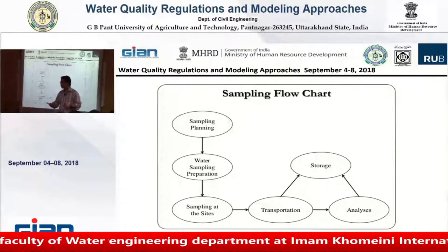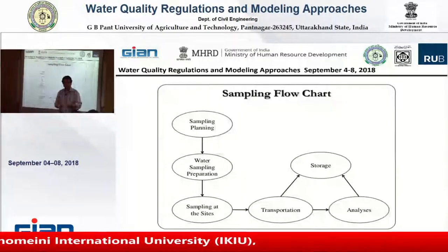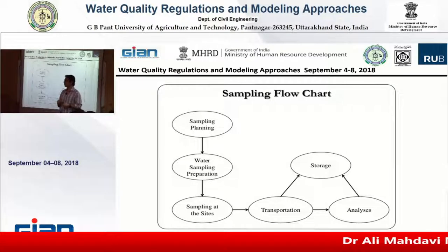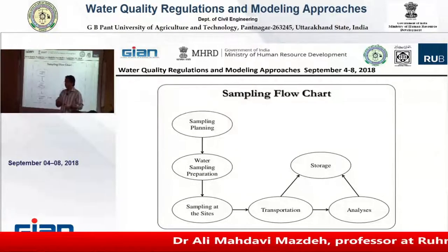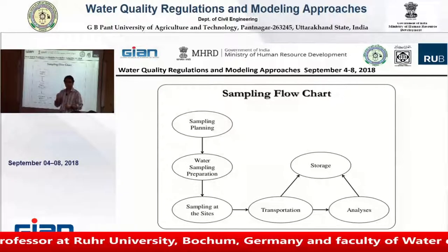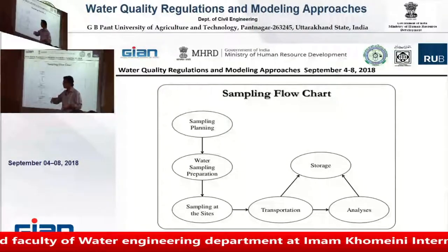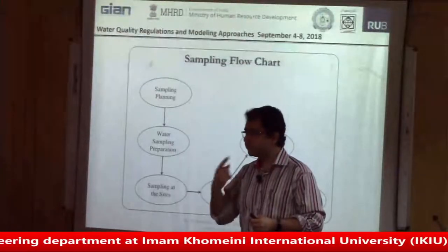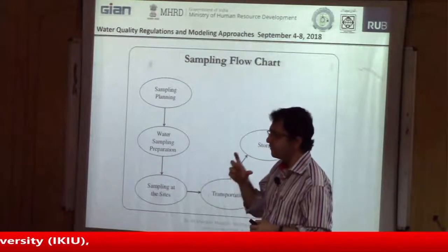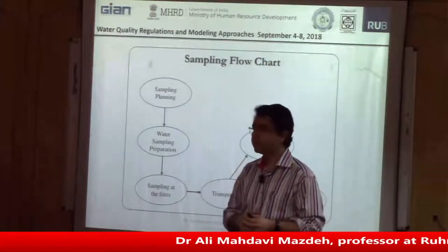After a certain period, 6 months, one year, it depends, 3 months, you should check them, you should calibrate them, because electronic devices, especially in the measurement of water quality, easily lose their precision, and they cannot measure very precisely. They need to be recalibrated. So remember always, when you have a device for measuring and you want to put it there forever, it's not a true way.